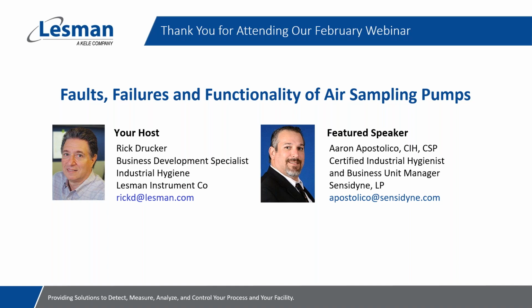Kind of related. Next question is, are Bluetooth equipped GilAir Plus pumps new? This person would like to use the app on their phone. So you have to have a GilAir Plus Bluetooth model pump. If you have one of our older GilAir Plus pumps, we do actually offer upgrades through our service center where you could send that in and we can upgrade it to a Bluetooth model for a fee.